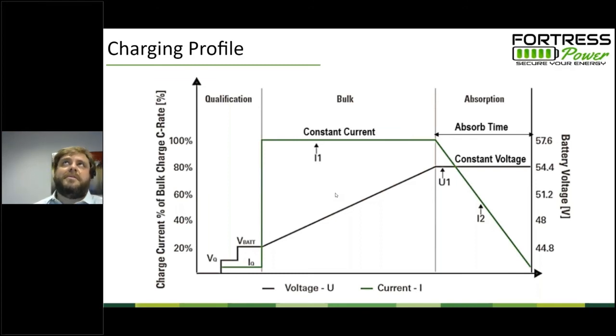That's not completely true. There are specific instances when we use equalization to, say, reset the calibration of the onboard battery management system computer, but that's not like a regular maintenance equalization charge like you would apply to an unsealed lead acid battery. And so regardless of what inverter or inverter setting you're using, what you're looking for is a 2-stage charge cycle, a bulk stage and an absorb stage, and you're trying to disable everything else.